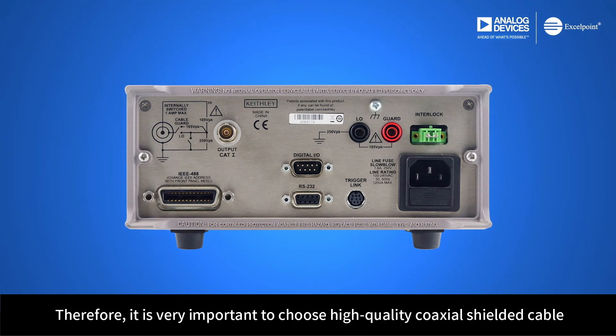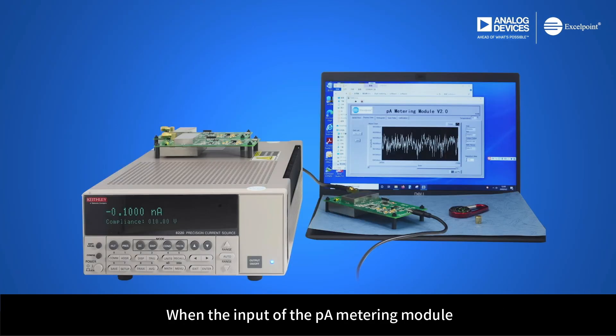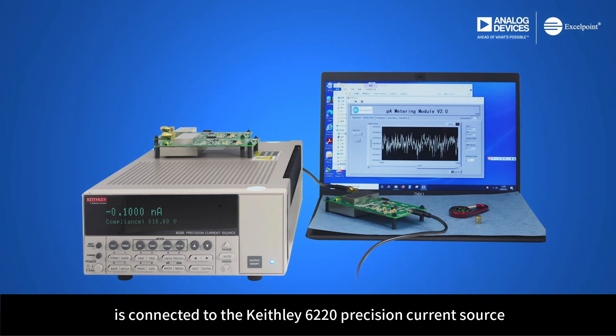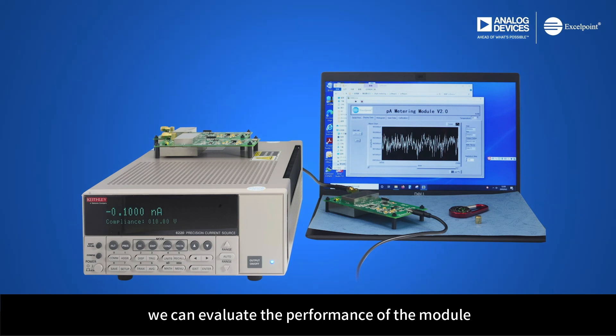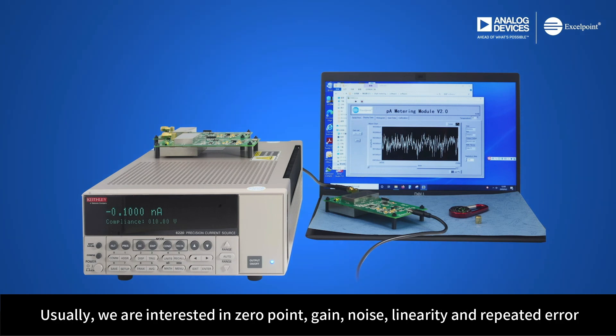Therefore, it is very important to choose a high-quality coaxial shielded cable. When the input of the PicoAmpere metering module is connected to the Keithley 6220 precision current source and the module USB is connected to the PC, we can evaluate the performance of the module. Usually, we are interested in zero point, gain, noise, linearity, and repeated error.